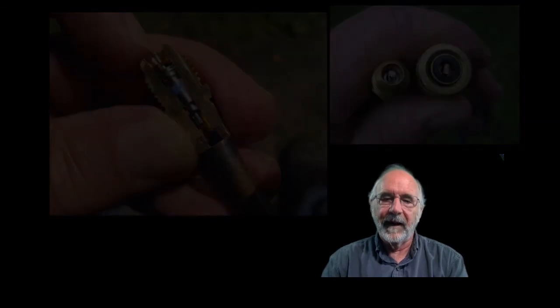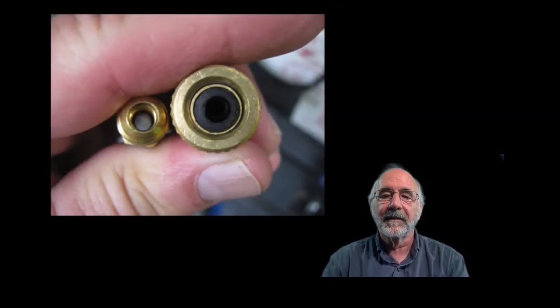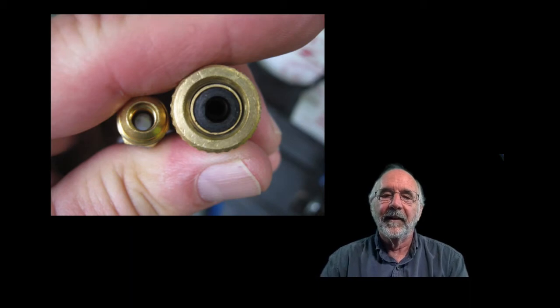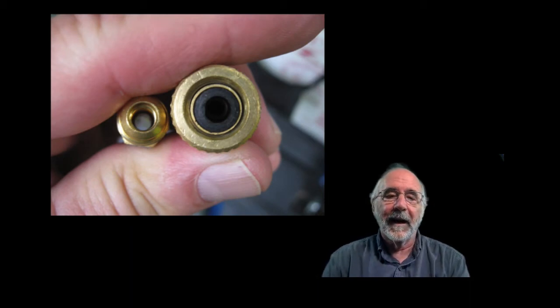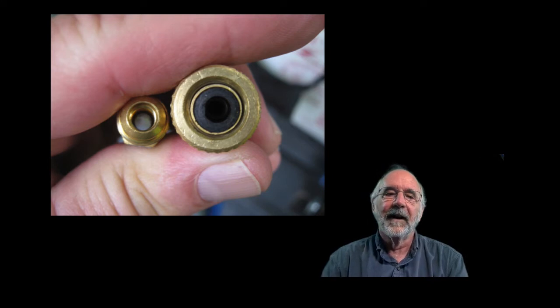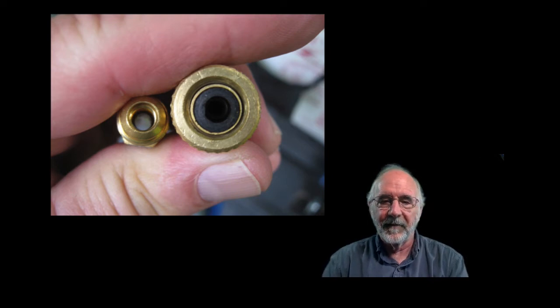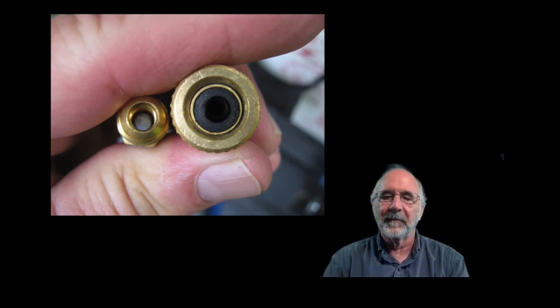Over-tightening the hose fitting crushes the gasket, pushing it out into the opening to block it off further, and then it damages the gasket itself, which then leads to further tightening of the fitting, and it just keeps spiraling out of control.